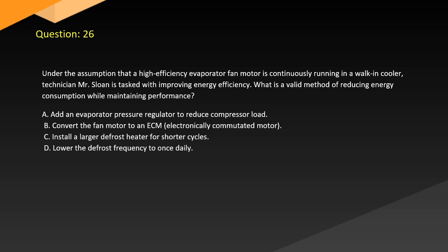Question 26. Under the assumption that a high-efficiency evaporator fan motor is continuously running in a walk-in cooler, technician Sloan is tasked with improving energy efficiency. What is a valid method of reducing energy consumption while maintaining performance? A. Add an evaporator pressure regulator to reduce compressor load. B. Convert the fan motor to an ECM, electronically commutated motor. C. Install a larger defrost heater for shorter cycles. D. Lower the defrost frequency to once daily.